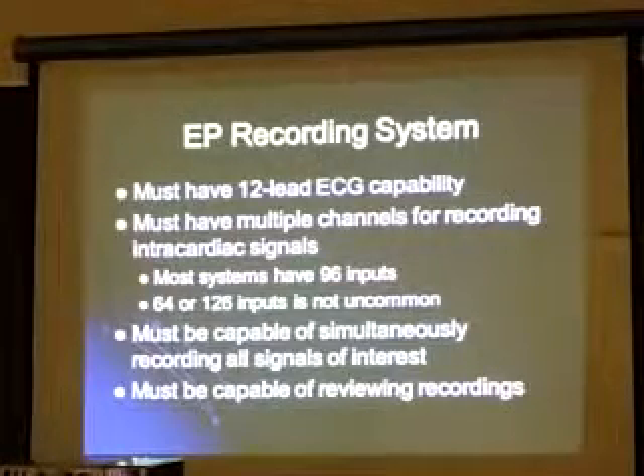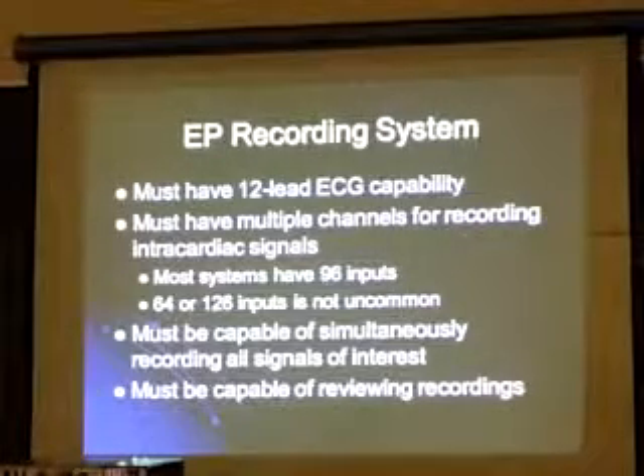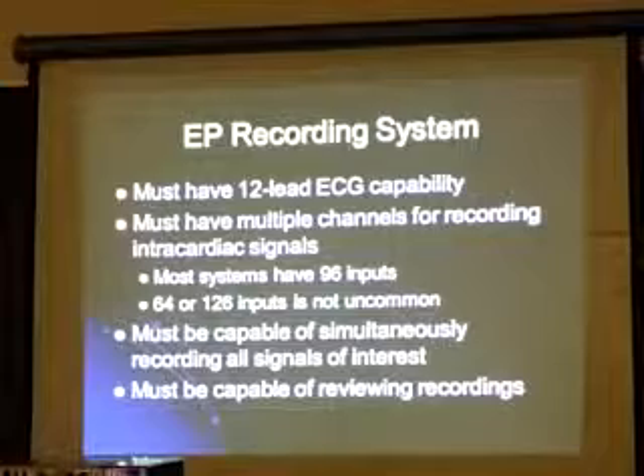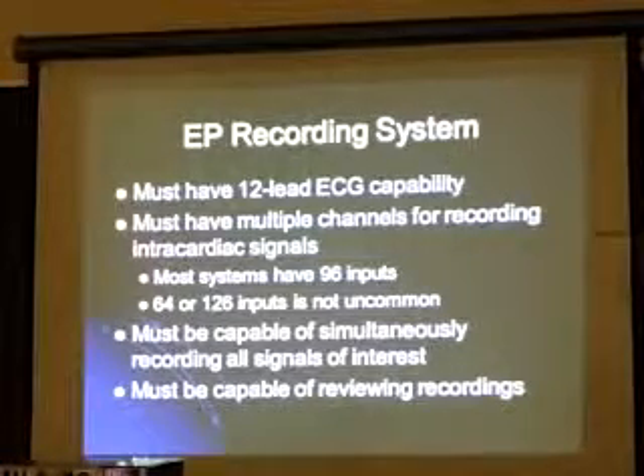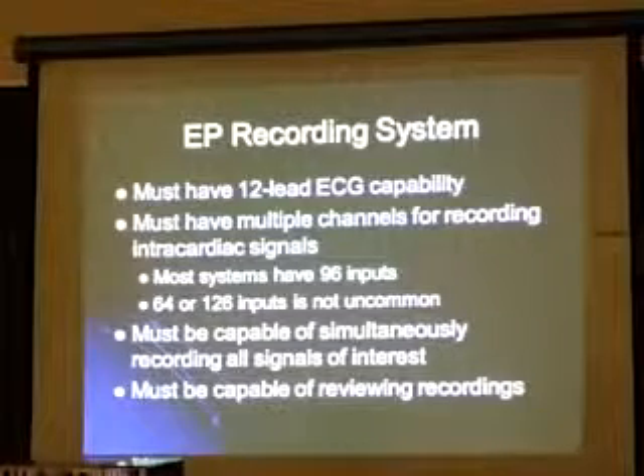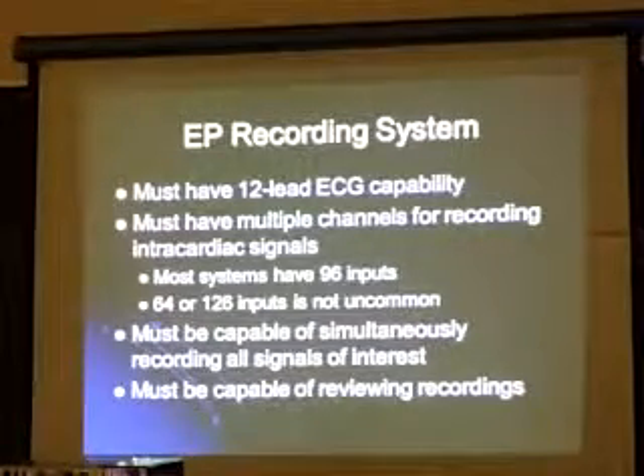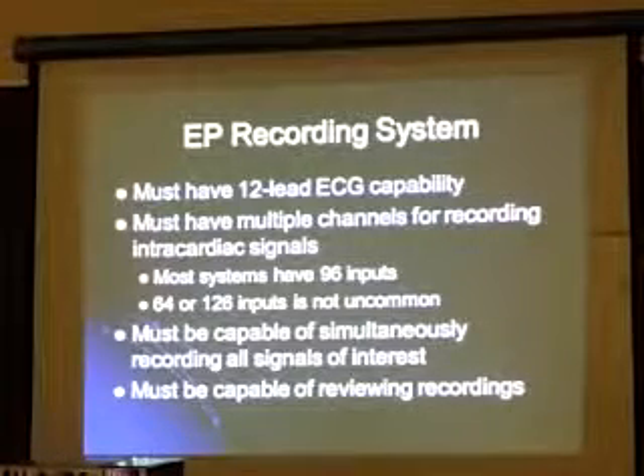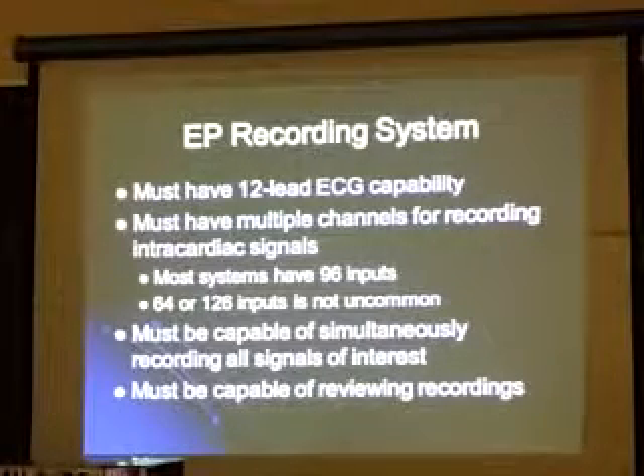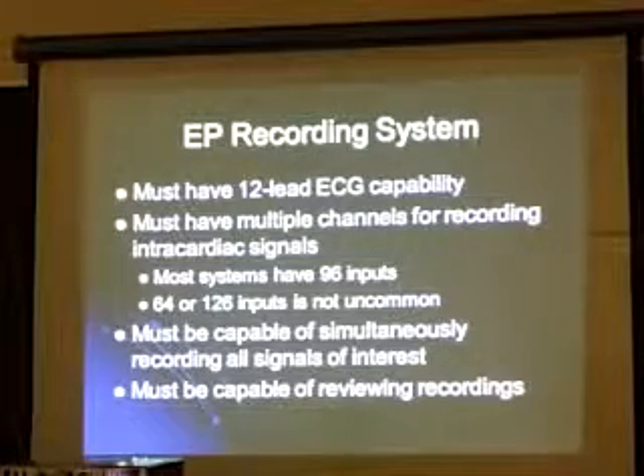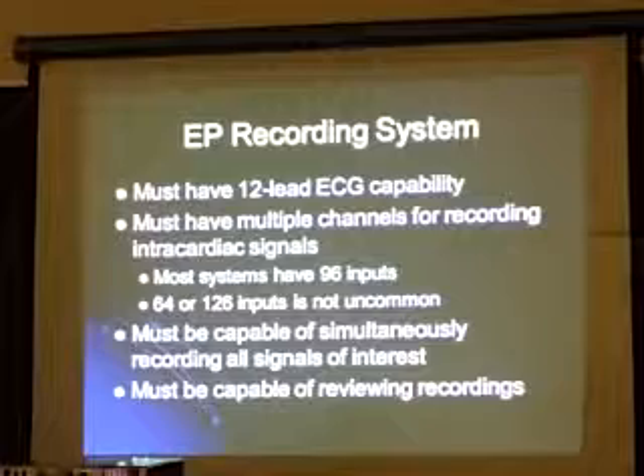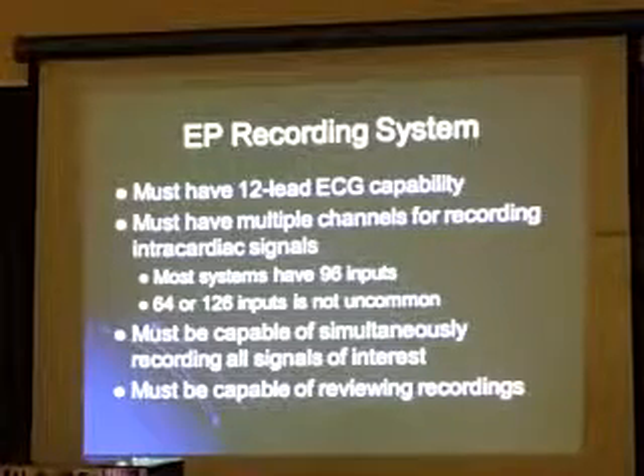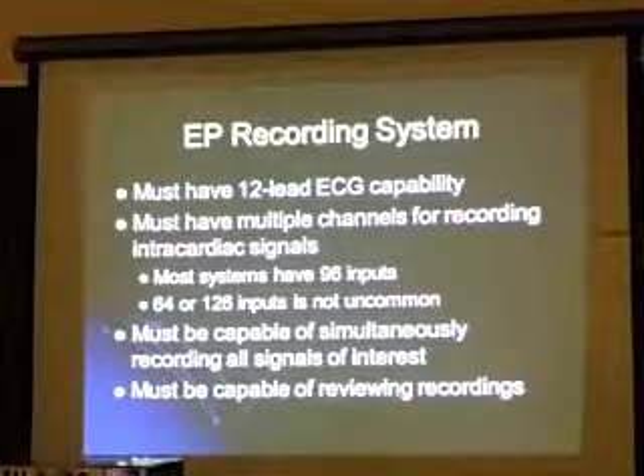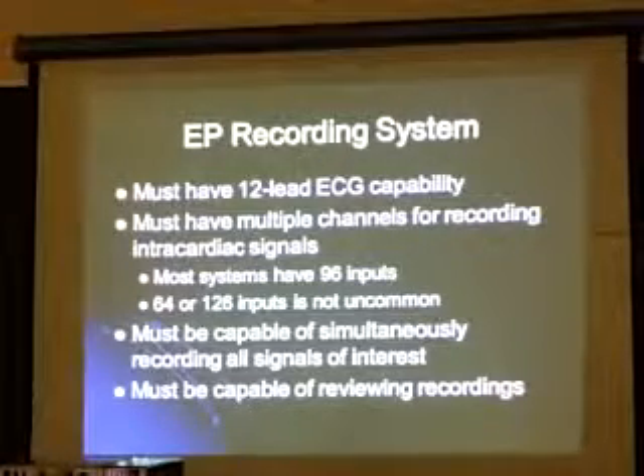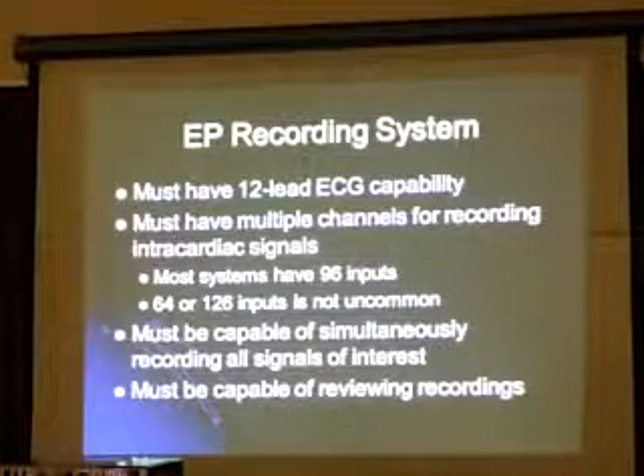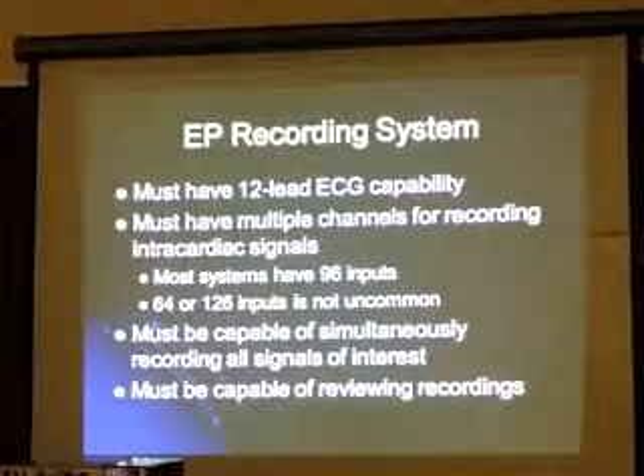You have to be able to record these signals simultaneously, and you have to do it at a very, very fast sampling rate. The minimum sampling rate, by at least my company's standards, is 1,000 times per second. You've seen how we stretch the signals out. At 1,000 times per second, you have to have a sweep speed of 150 millimeters per second in order to see all of the information that we're gathering. I do have some research labs that I work with that are sampling at 2,000 and 4,000 times per second, but that's only research.